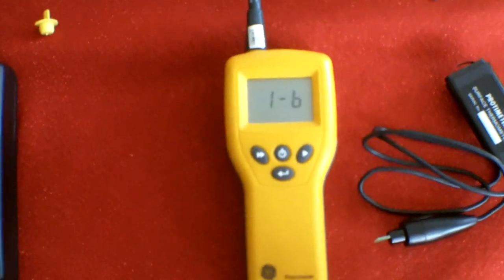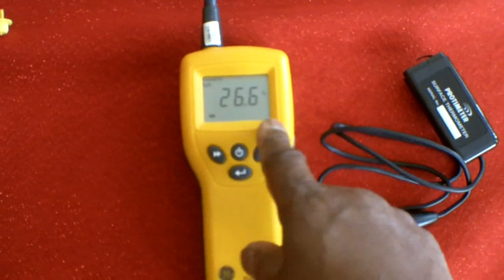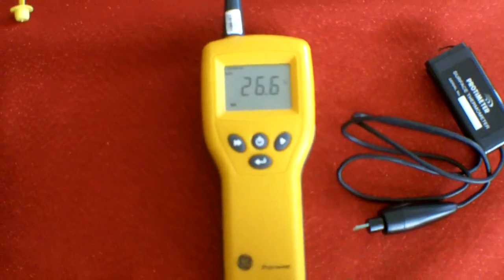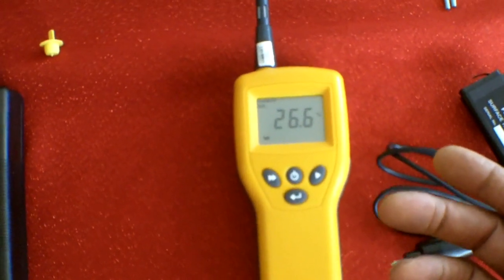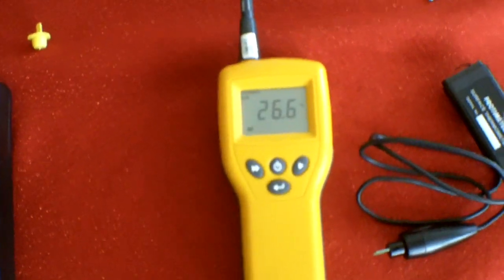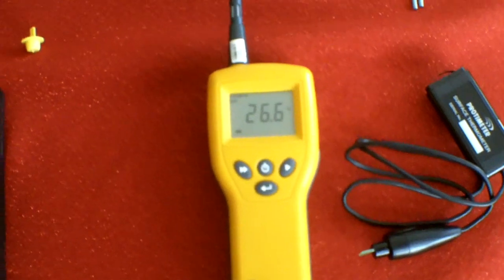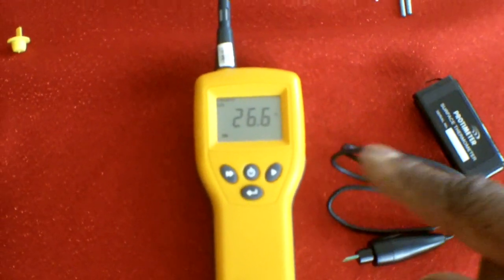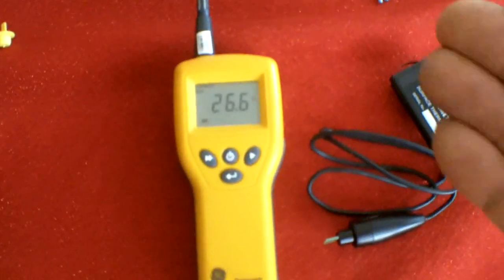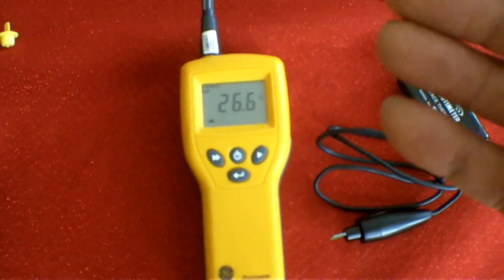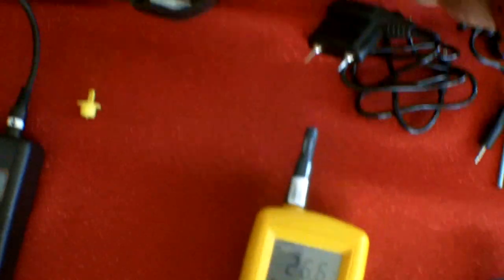Let me just switch this on to see if it'll come on. Alright, so now that's come on, it's going to give you the relative humidity. The relative humidity it's saying is 26.6, and you think, well, what does that mean? Basically it's saying that the amount of moisture which is held in the air is relative. It's 26%, 100% is saturation. It doesn't mean that it's going to rain. It's just that when the temperature drops, depending on what the dew point is, which is the point at which the place cools, then you would get condensation on the surface. So this is what's known as a Protimeter, and there are various other attachments with it. This is an extension for that.